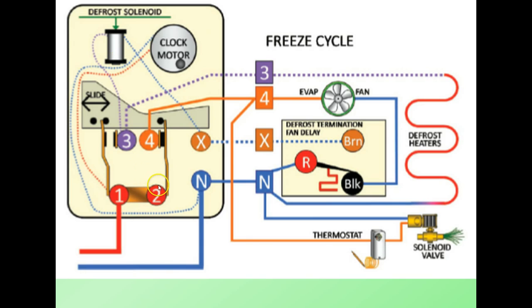The last load we're going to look at is the defrost heaters. They are always connected to neutral. Let's see where we are with our power. 115 volts comes to terminal 3, comes back down here to terminal 3, and terminal 3 is not made, so the defrost heaters are off.